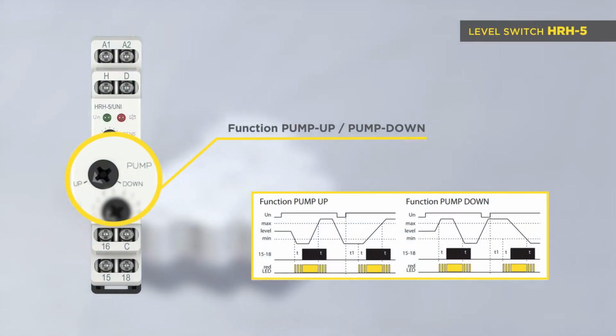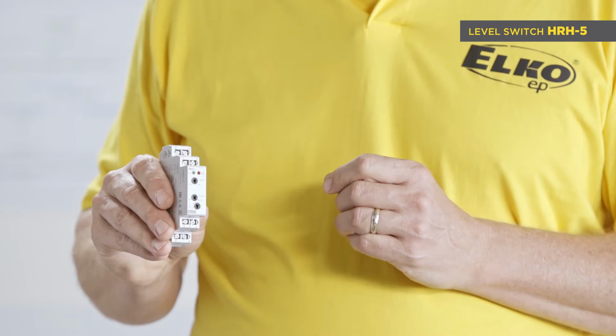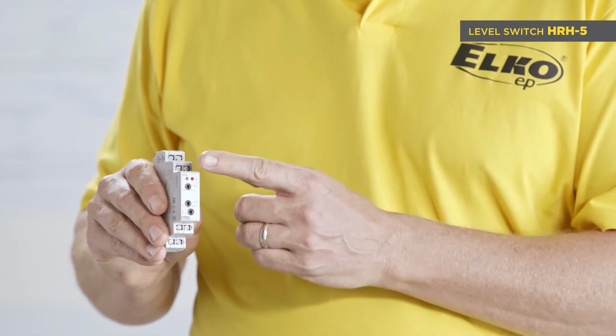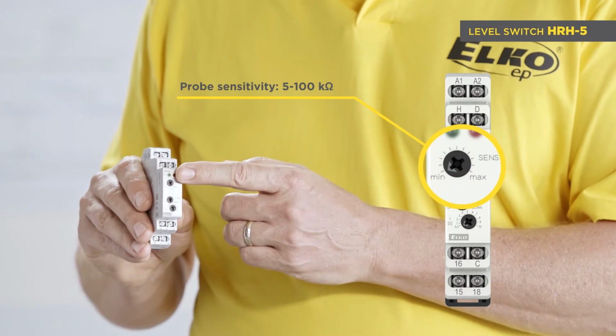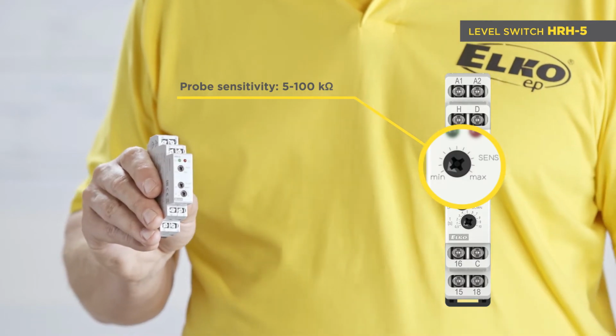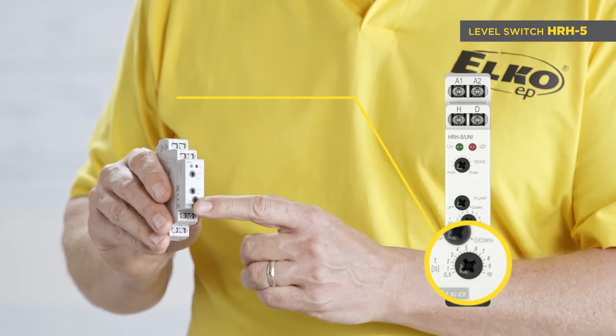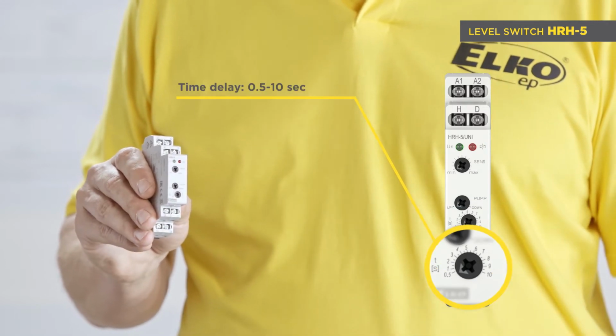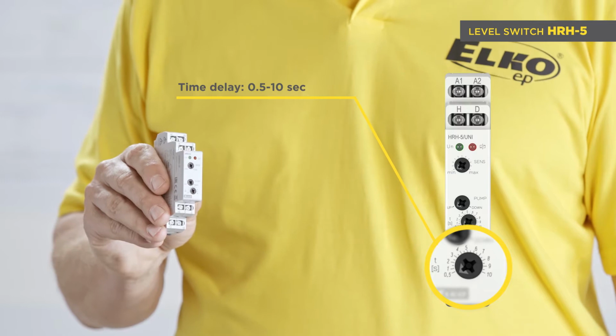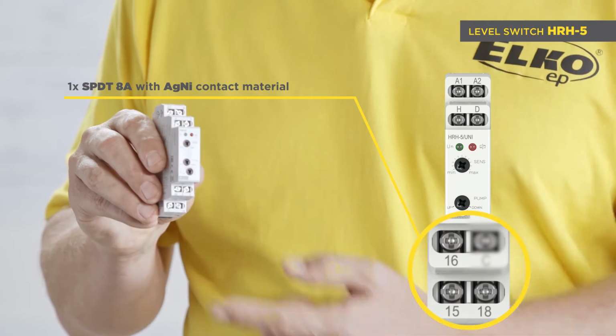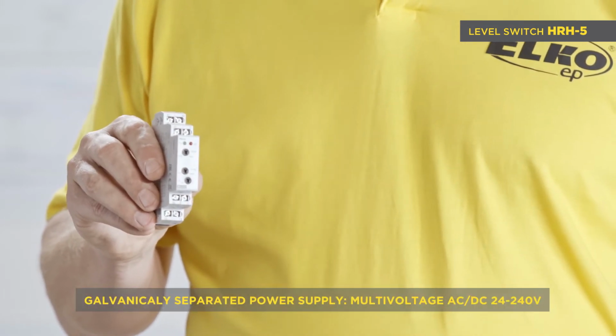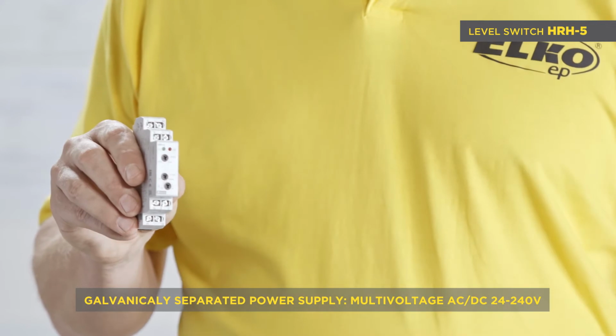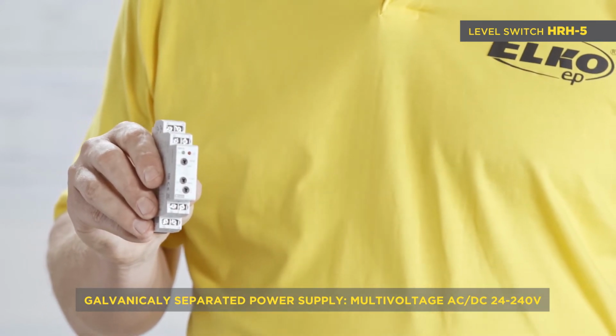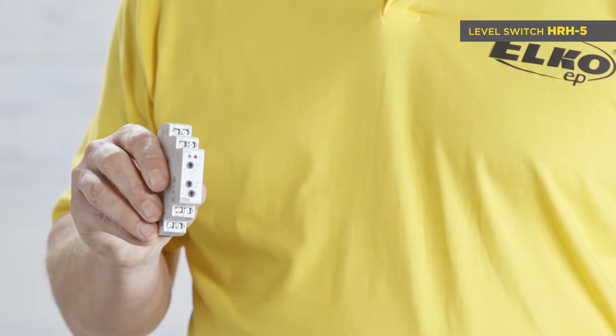HRH5 is the basic level switch with the function pump up, pump down, adjustable from the front panel. There are also two more setting potentiometers. One for probe sensitivity setting in a range of 5 to 100 kilo ohms, and the second for time delay setting in a range of 0.5 to 10 seconds for elimination of waves on the surface. One output relay has an SPDT changeover contact 8 amps. It features a galvanically separated power supply from the measuring inputs in multi-voltage range of AC/DC 24 to 240 volts.